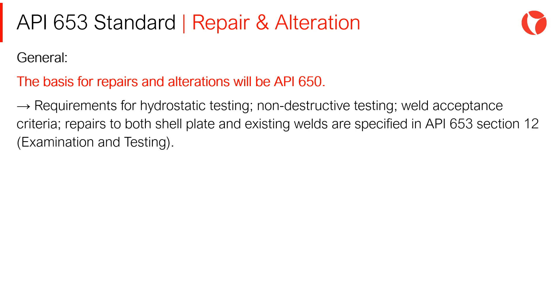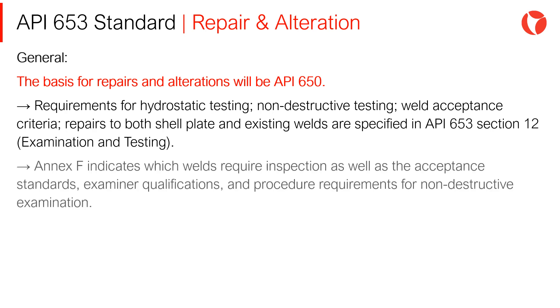Requirements for hydrostatic testing, non-destructive testing, weld acceptance criteria, and repairs to both shell plate and existing welds are specified in API 653 standard section 12. Annex F indicates which welds require inspection, as well as the acceptance standards, examiner qualifications, and procedure requirements for non-destructive examination.